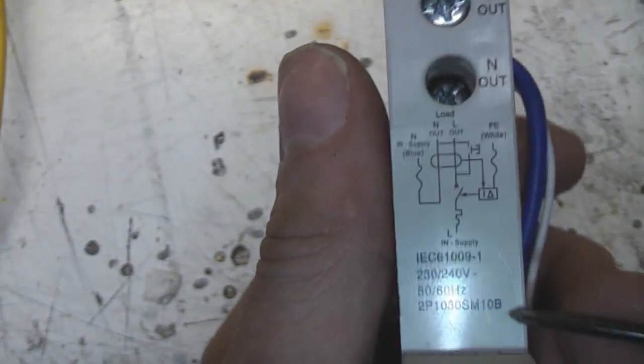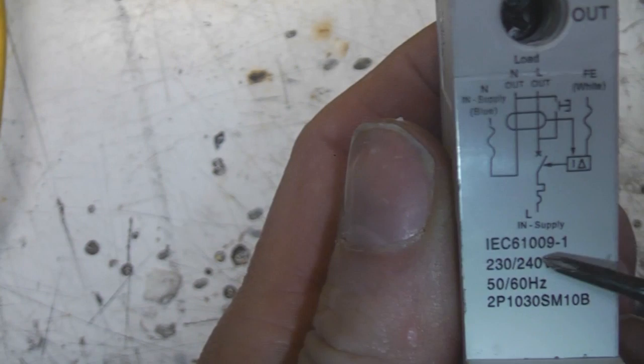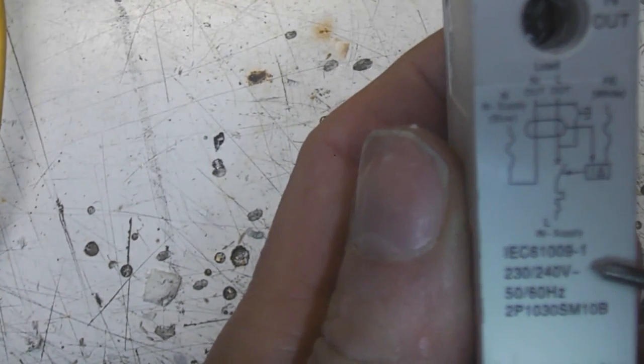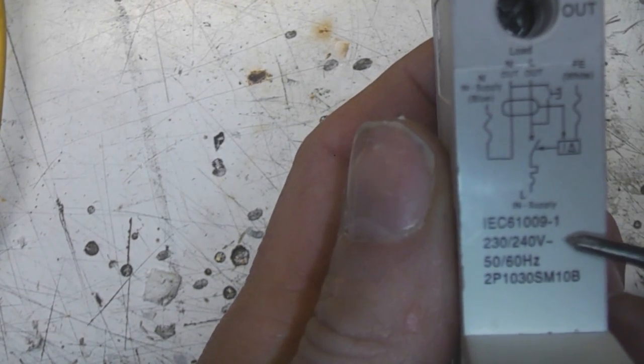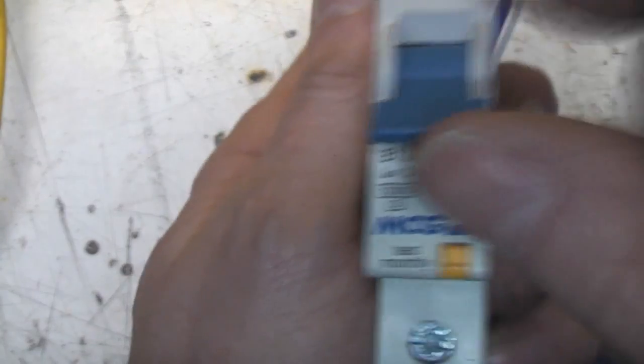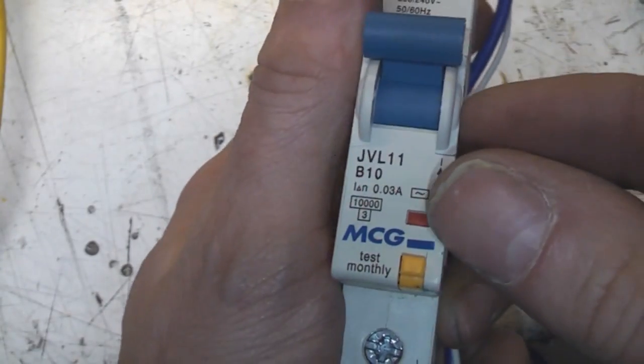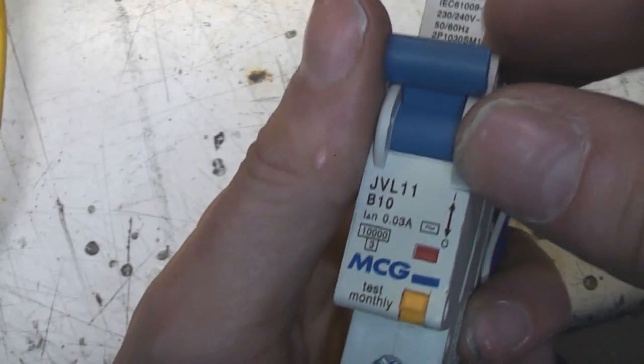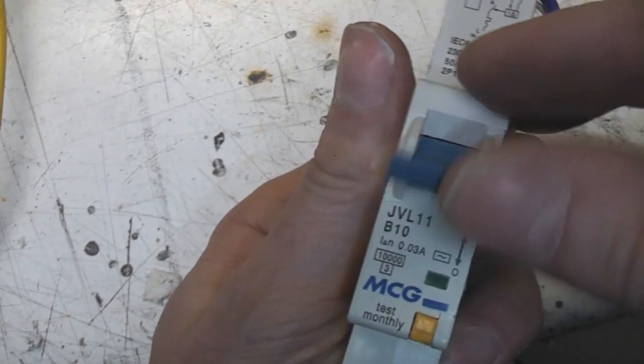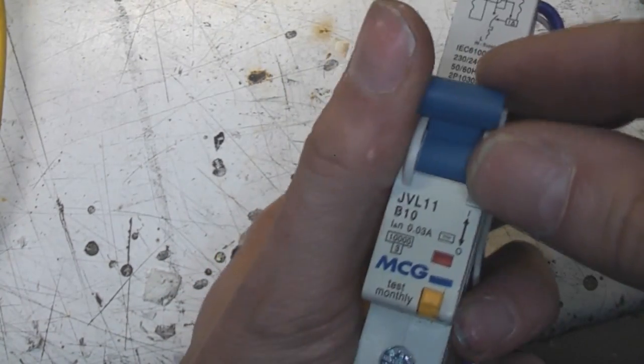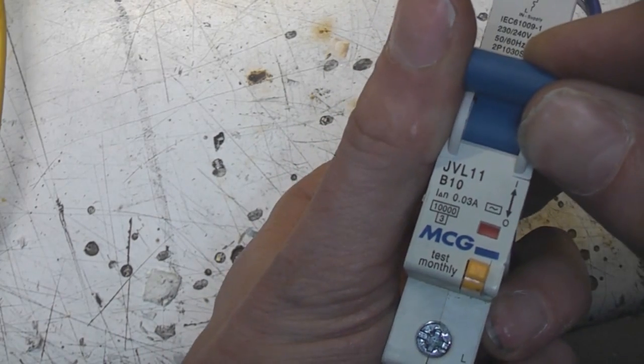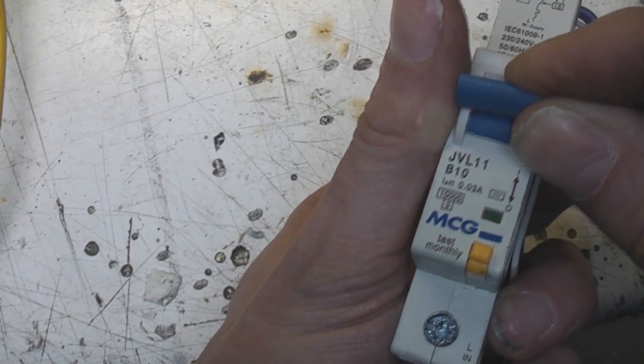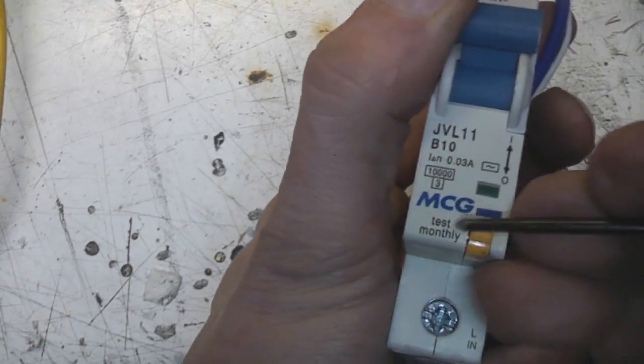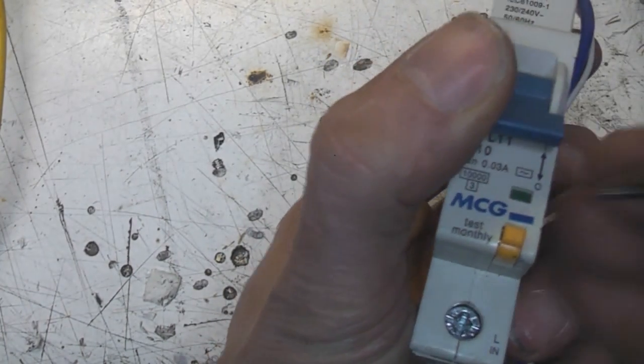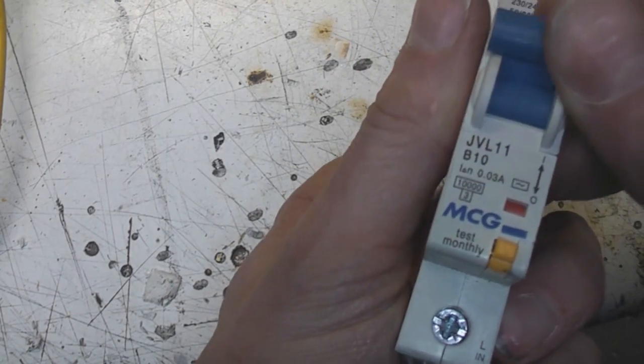There's a number of various markings on here, IEC 61009, which is the standard that it's designed to. We've got the on-off, and this flag shows the actual status, because one thing about circuit breakers is they're designed so that you can't just hold them on, because they will trip internally. If I move that slowly back, you'll see it will go to a trip state. So even though I'm turning it back on, it's still off, and the green flag has to go all the way off to reset it.